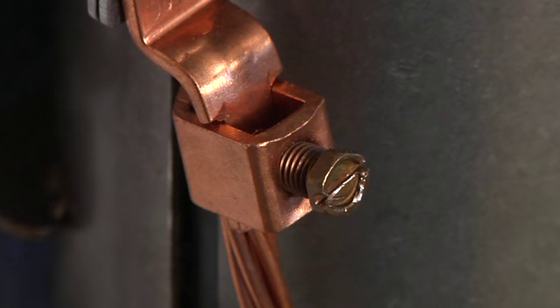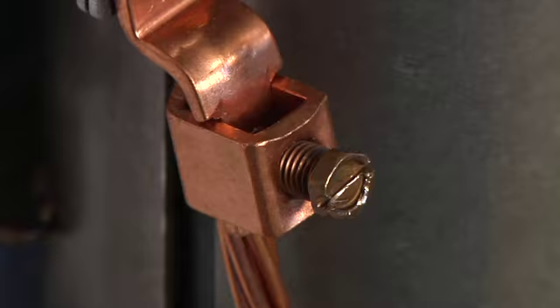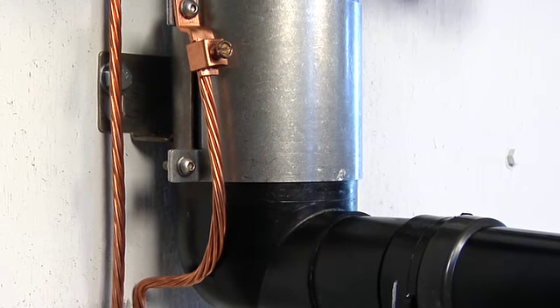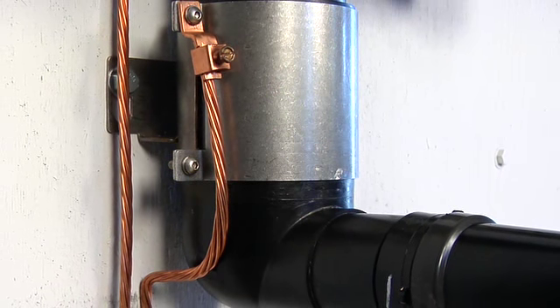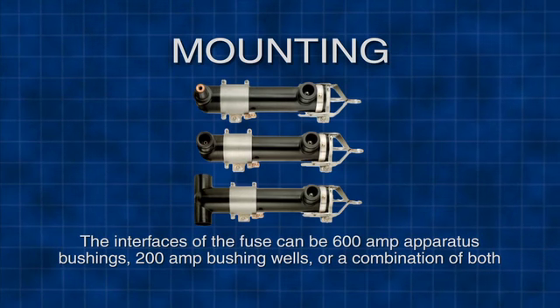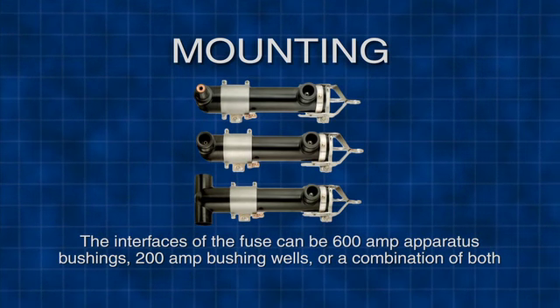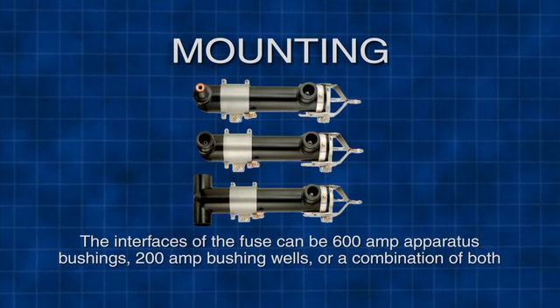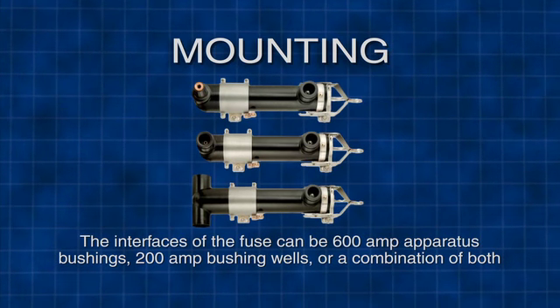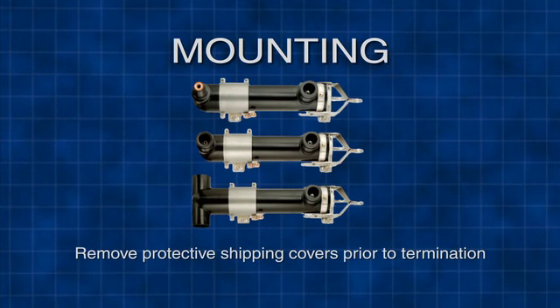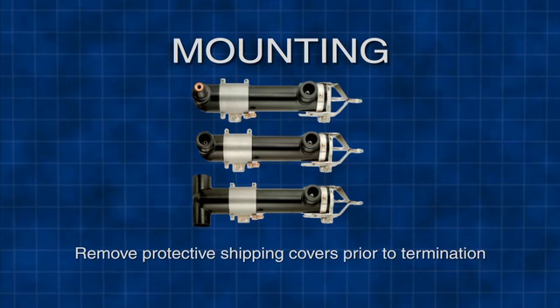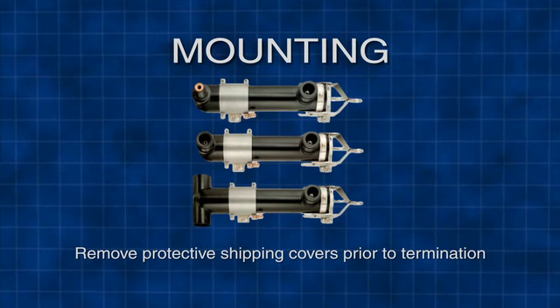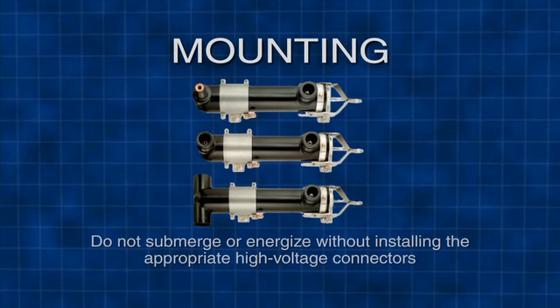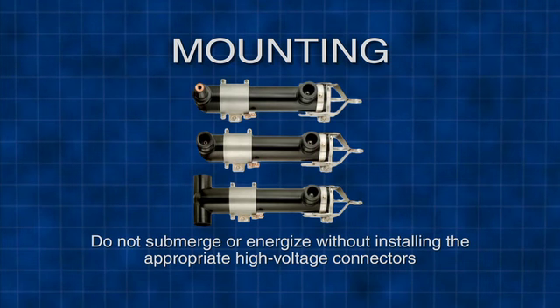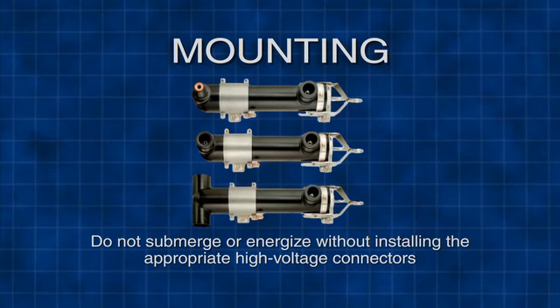2 ground lugs are provided for the fuse ground. The fuse ground and all cable shields must be properly attached to the system ground. The connection interfaces of the fuse can be 600 amp apparatus bushings, 200 amp bushing wells, or a combination of both. Protective shipping covers are used to protect the bushings during shipping and should be removed prior to terminating the cable. Do not submerge or energize without installing the appropriate high voltage connectors.